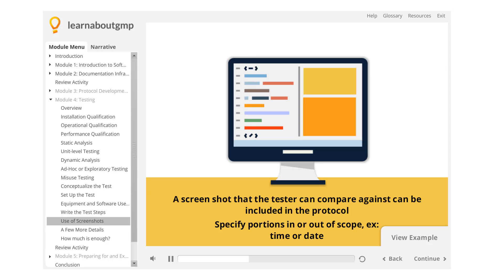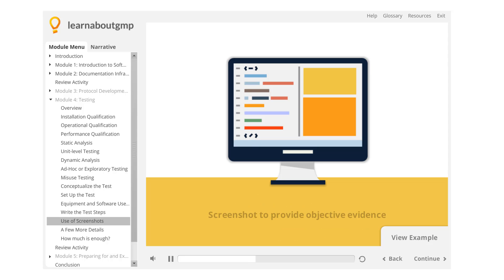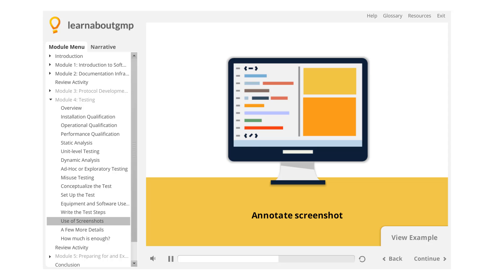The above example relies on the tester to make a pass or fail judgment based on what he or she sees. An alternate approach might be to have the tester take screenshots and provide objective evidence of passing steps. Judicious use of screenshots provides good supporting data. Gratuitous use of screenshots, though, can be a real headache. Each screenshot needs to be properly annotated to link the results to the test. It's easy to overdo screenshots, so be aware of the overhead. It's recommended to give the user explicit instructions when screenshots are called for.